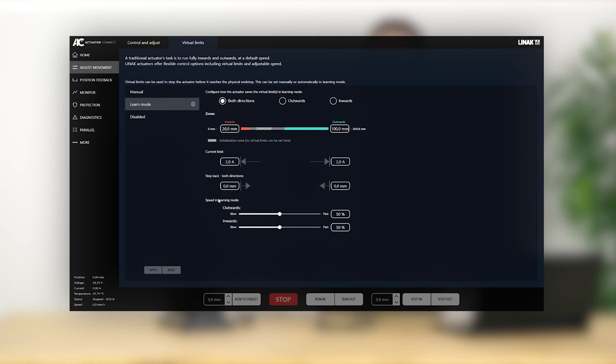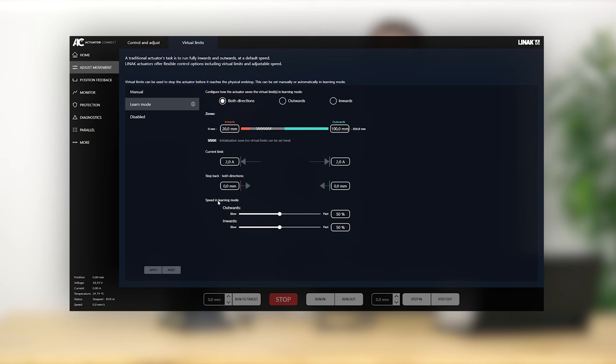It's also possible to specify a speed setting for when the actuator is running in learn mode, in case you'd like to run slower when learning an obstruction. Learn mode can be performed directly in Actuator Connect or by shorting the red and black wires in sequence.